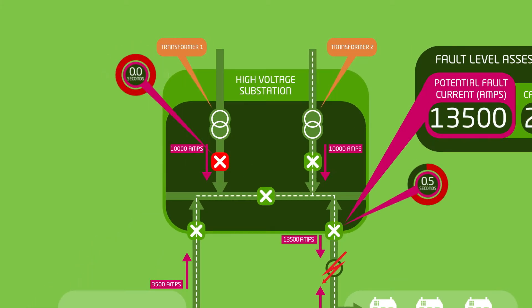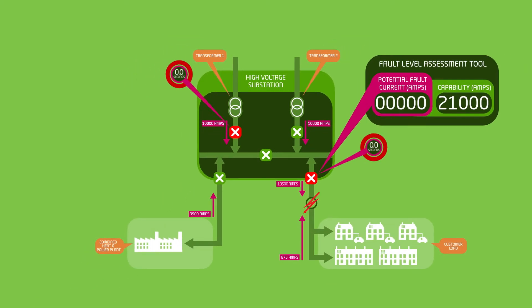Here, the circuit breaker on transformer one trips one second after a fault, taking away 10,000 amps from the fault current, enabling the existing high voltage circuit breaker to operate within its capability. After half a second, the HV circuit breaker trips. This sequence tripping allows the existing equipment to manage a network with higher fault currents than it was designed for.